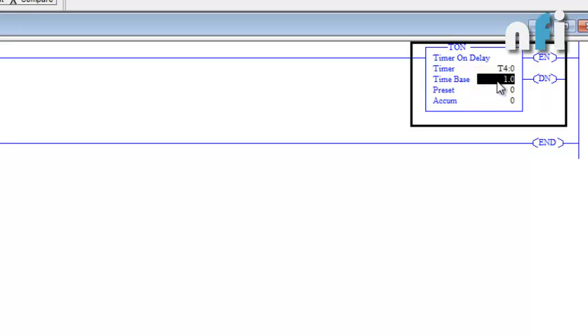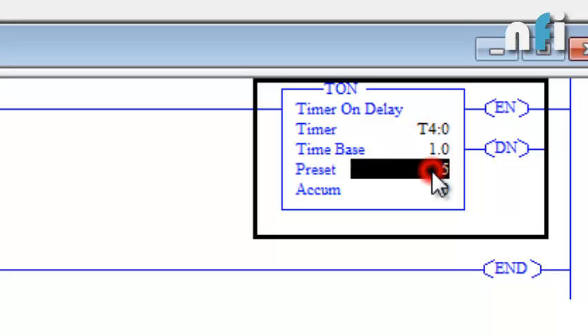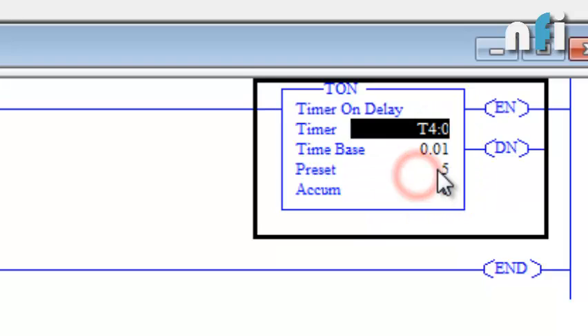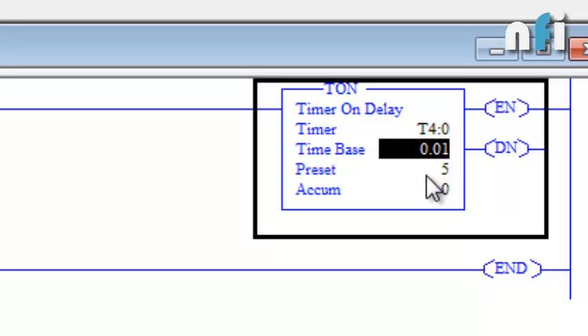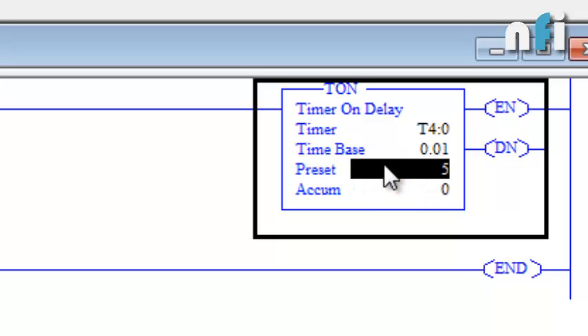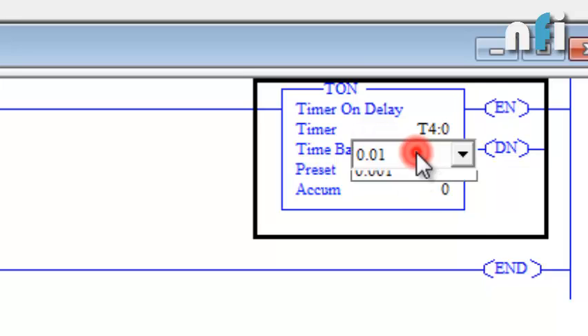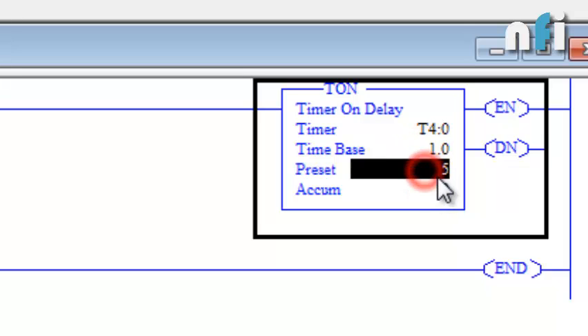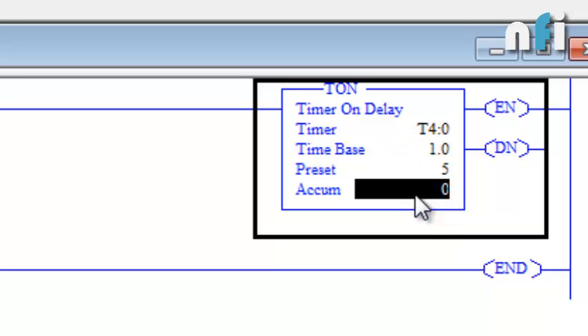Next is the time base. Time base means the minimum count which a timer will count — 1.0 means one second. The preset is the time which we want for the delay. If I'm entering 5 here, that's 5 multiplied by the time base 1.0, which equals 5.0 seconds. If I change the time base to 0.01, then 5 x 0.01 = 0.05 seconds. So you can change the time delay using the time base. The accumulator is the time which the PLC counts when the timer starts.